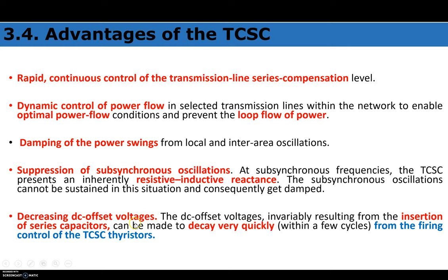Another advantage is decreasing DC offset voltages. When only a fixed capacitor is in the operating mode, it produces DC offset voltage. TCSC decreases this DC offset voltage — the offset invariably resulting from insertion of series capacitors can be made to decay very quickly within a few cycles through the firing angle control of the TCSC thyristor. The thyristor controlled reactor can be switched on immediately to damp those DC offset voltages produced by the fixed capacitor.